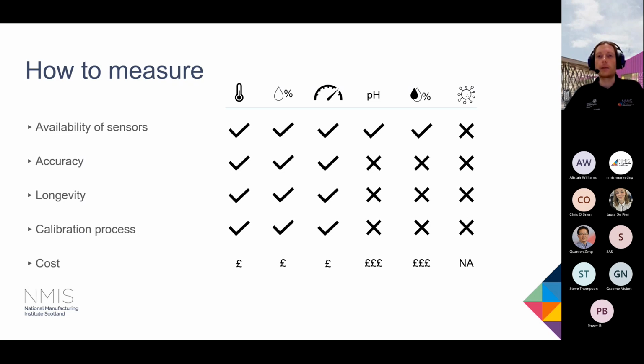pH was a bit more challenging. There are pH sensors available, and they may be reasonably accurate once calibrated, but I've marked them down on accuracy because we're looking at a device you can fit and leave in your coolant tank without worrying too much. If you don't continually maintain it, the accuracy wanders. These pH sensors, being so sensitive, need to be stored in a pH neutral solution, calibrated before every single use, and cleaned off after every use. So for something left sitting in a tank, it doesn't really tick the boxes for accuracy, longevity, and calibration processes. Similar with the concentration measurements.